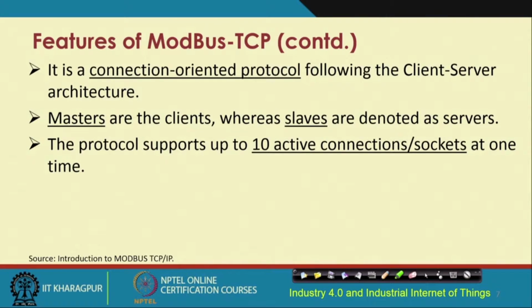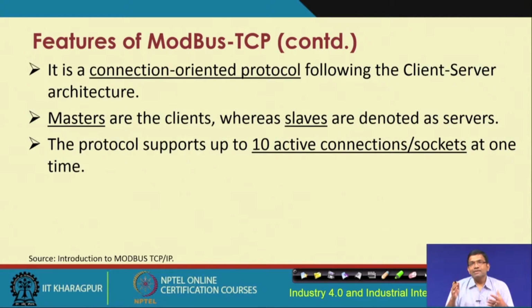So, in the same way as masters ask the slaves to do certain work, here also the clients ask the servers to do certain work, and the servers respond back in the same way as the slaves would do the work and respond back to the masters. Here also the servers respond back. So, Modbus TCP basically supports up to 10 active connections or sockets at one time.